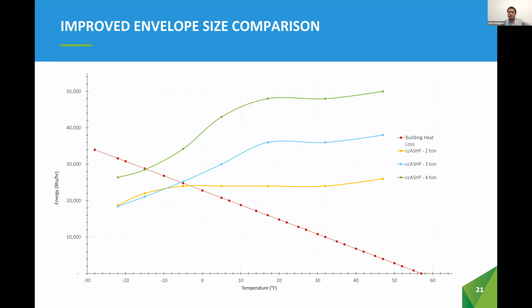Now, taking those same 3 cold climate units from earlier and comparing them to a similar premise, but with an improved envelope, which reduces the home's heat loss from 50 MBH to 34 MBH, similar to the NBC 2020 Tier 1 levels. With the reduced load, the rated heating capacity of the units at 47 degrees Fahrenheit or 8 degrees Celsius is as follows. The 2 ton meets 71% of the building's heat loss. The 3 ton meets 103% of heat loss, and the 4 ton 141% of the heat loss.